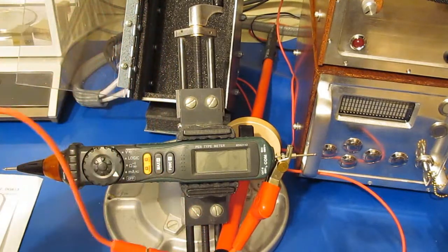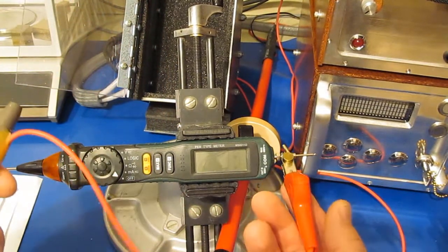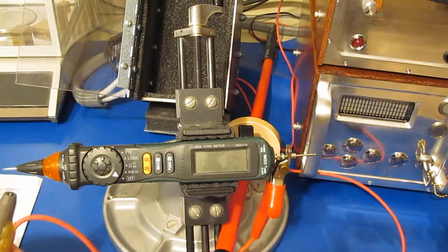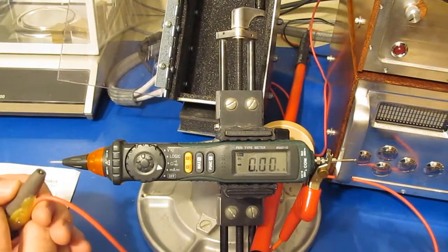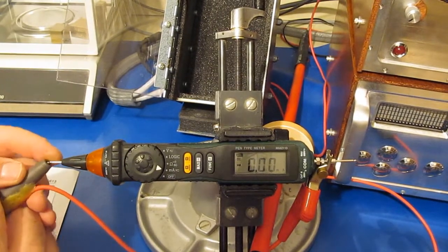Next we'll go ahead and perform our static test. You can see I'm basically just clipping straight across the meter. Again I'll apply 5 transients both positive and negative.